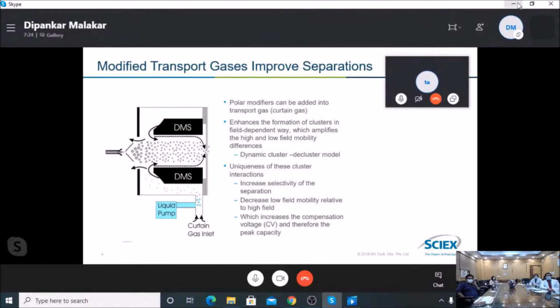gas molecule, what is called transport gas, like isopropyl alcohol, acetone, or ethanol — these are the very common modifiers used, which are introduced in the gaseous phase into the cell and interact with the molecule differentially, so that their ion mobility characteristics change. Because of the introduction of this gas molecule or gas pressure, the COV value differs in this condition. So COV value differing means we are able to achieve the required separation of the molecule — increased selectivity of the separation, decreased low field mobility relative to high field, which increases the COV, compensation voltage, and therefore the peak capacity.